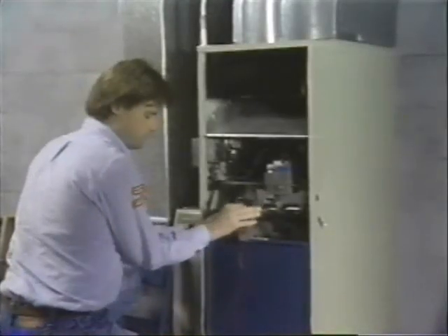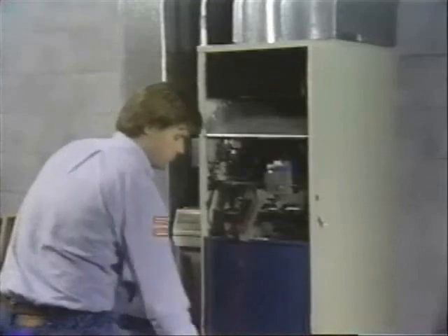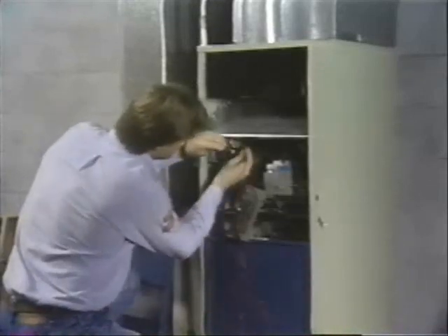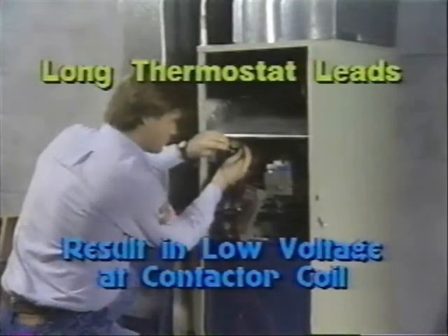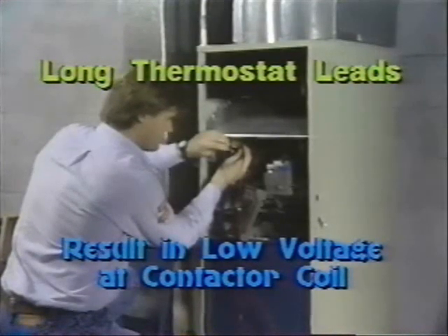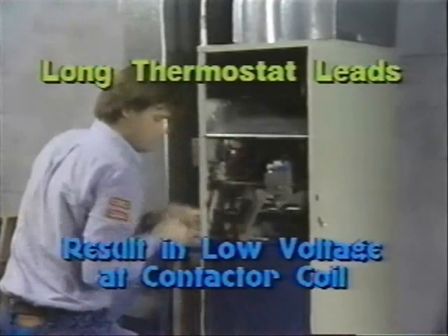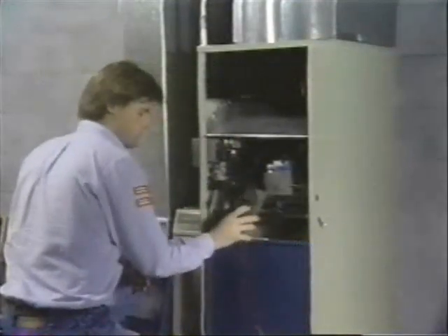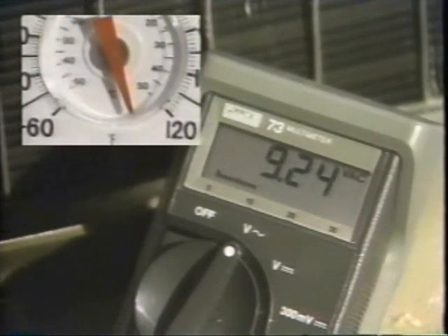Sometimes the location of the contactor may cause operating problems. If the coil voltage is low, check to see if the thermostat leads are too long. If line loss becomes excessive, it results in low voltage at the contactor coil. You may need to install heavier wire. High temperatures can also be a factor. For example, an area that exceeds 150 degrees Fahrenheit causes the coil to lose its efficiency and operate incorrectly.